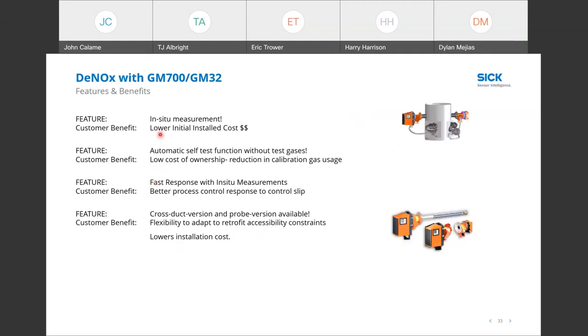But typically for both the GM700 and GM32, they are in situ measurements, so they do have a lower initial cost for installation and lower maintenance cost and lower cost of ownership and fast response because we're not modifying the sample. In situ, it's a very fast response time. And then we do have the different variants of cross-duct and the single probe.